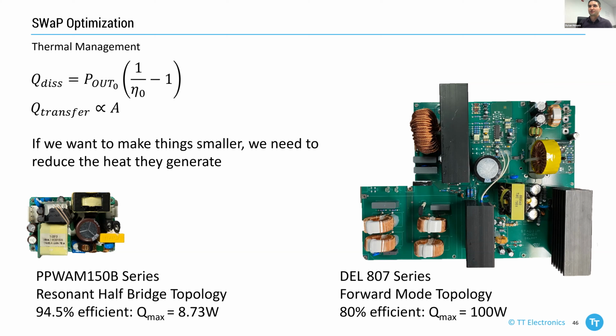Operating at 94.5% efficiency, we're only dissipating, worst case, a little less than 9 watts for the smaller supply. The larger supply, operating down at 80% efficiency best case, is dissipating 100 watts—almost as much as the first converter even generates or converts. So that's one way to reduce the size of your heat sinks: make sure you're operating more efficiently.